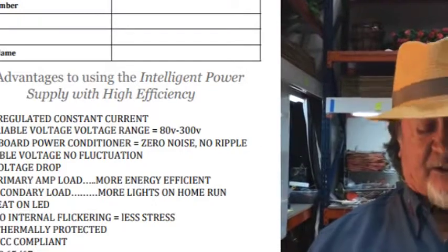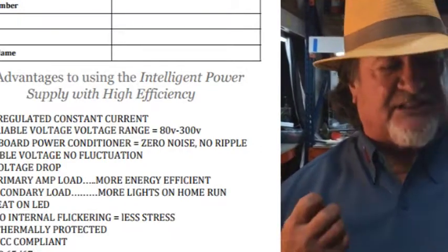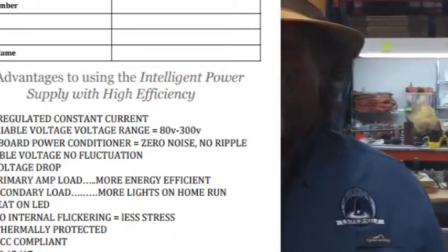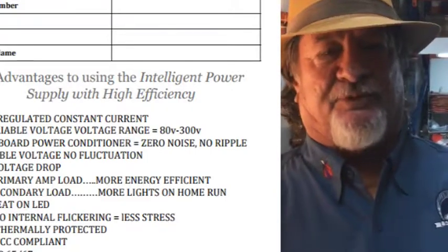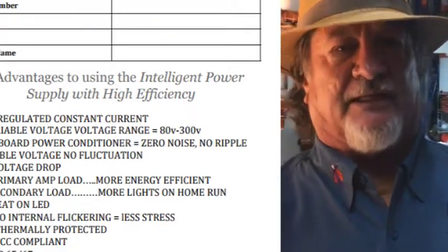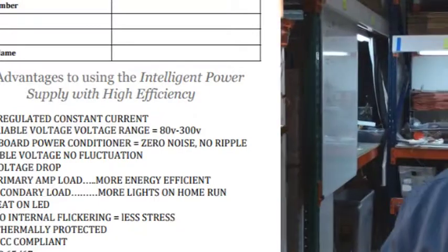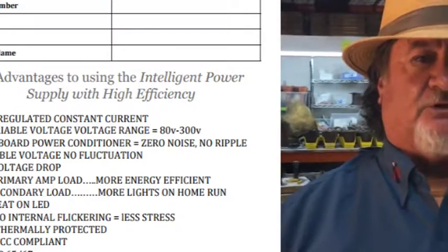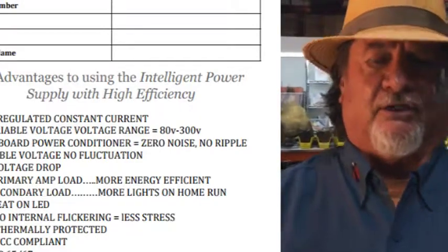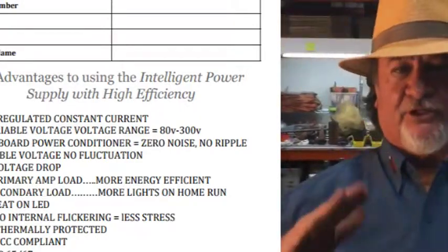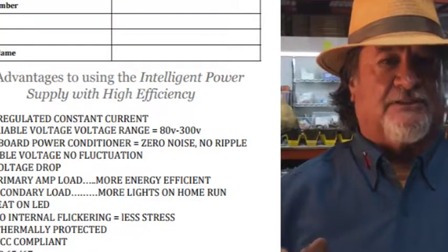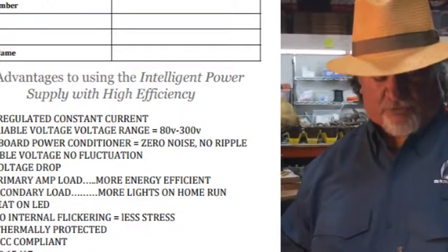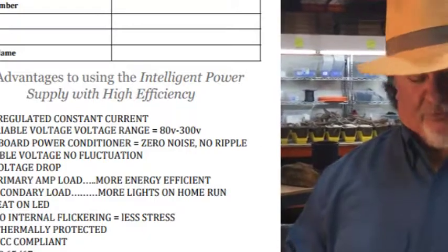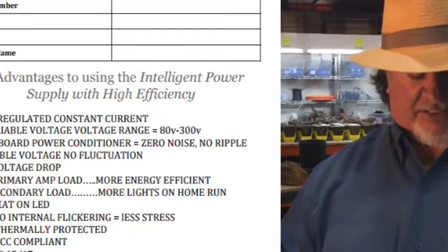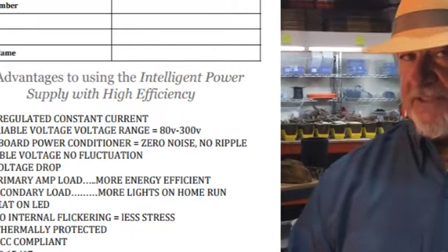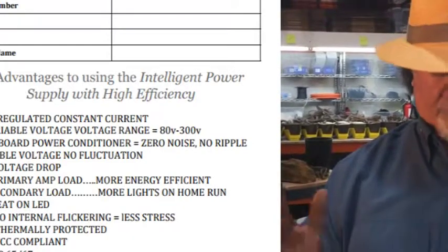It has an onboard power conditioner, right? LEDs are sensitive and they are smart. We cannot put them up and hook them up with a dumb magnetic transformer anymore. They need an electronic driver that conditions the power. LEDs don't like unstable voltage. They don't like 12.1, 12.2, 12.3, 11.9, various fluctuations. That's how a magnetic transformer works. They like constant conditioned voltage. Voltage is stable with no fluctuations. It's minimal. It has less voltage drop. Voltage drop's pretty much the same, but it has whatever that is, 20%, 30%.